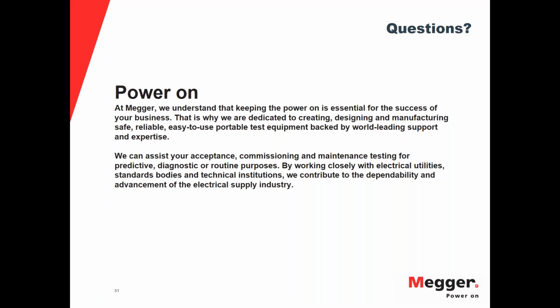The other reason the test is considered destructive is if you go below the minimum voltage, or the end voltage specified by the manufacturer, then the chemistry is going to be affected. In that case, you are definitely going to affect the ability of the battery to hold energy, so you're affecting the capacity. But as I mentioned during the presentation, if you handle the test properly and do things in the correct way, you're not going to be affecting the battery. So that is very important.